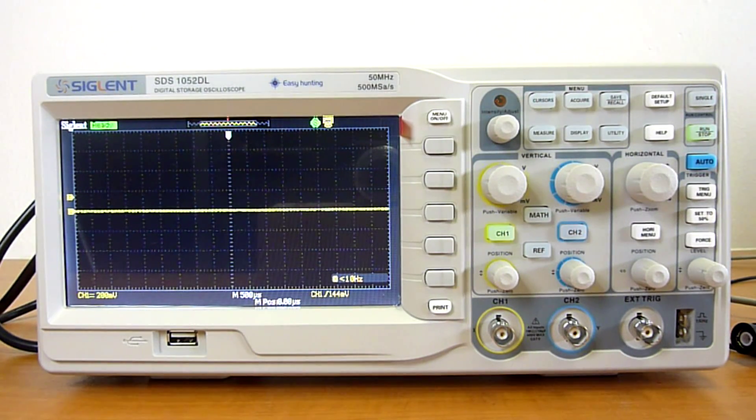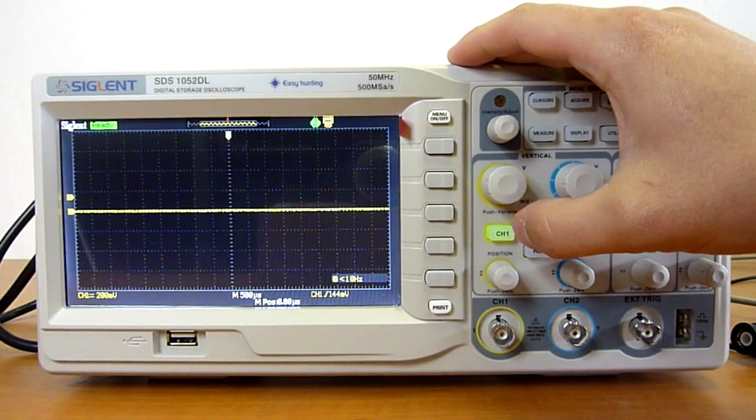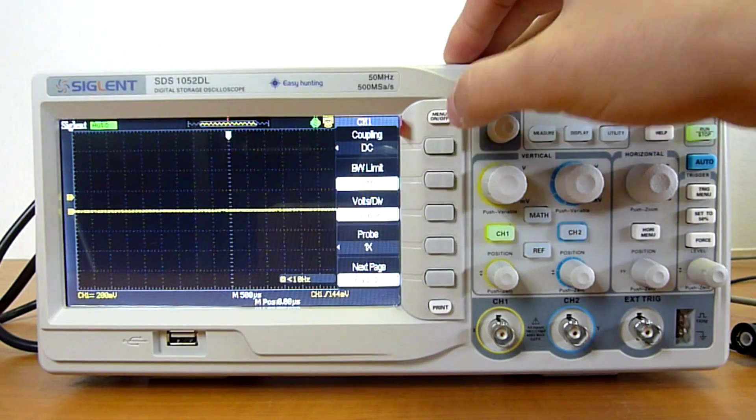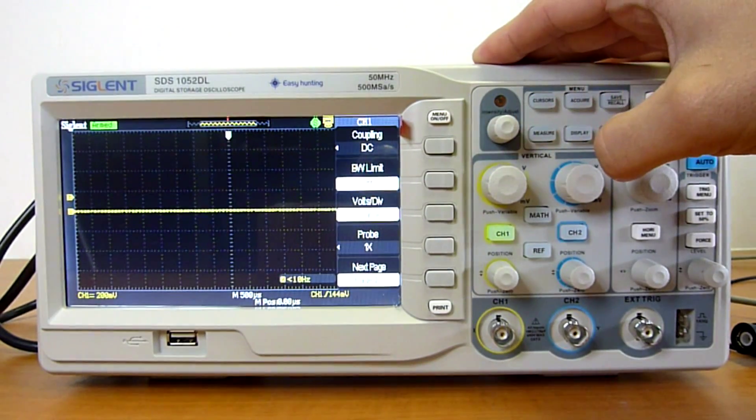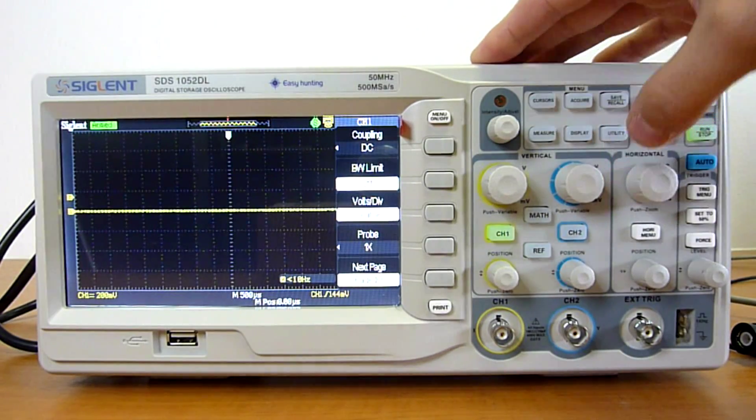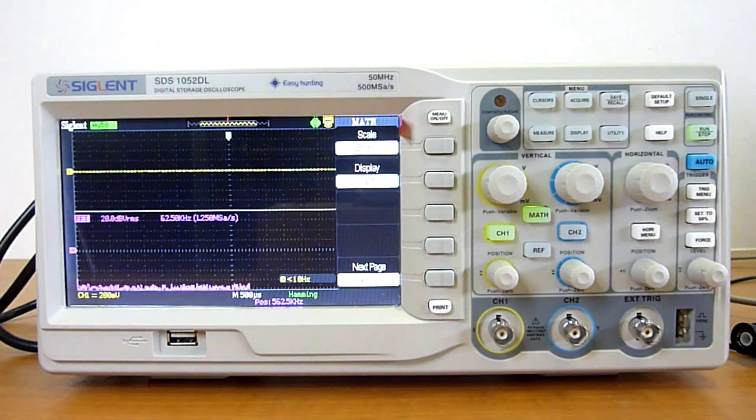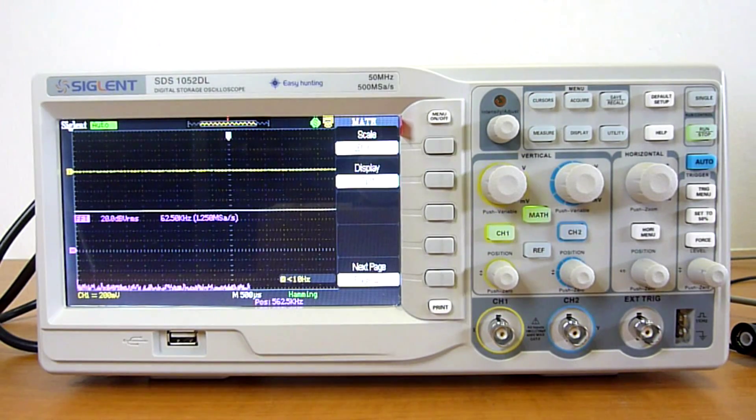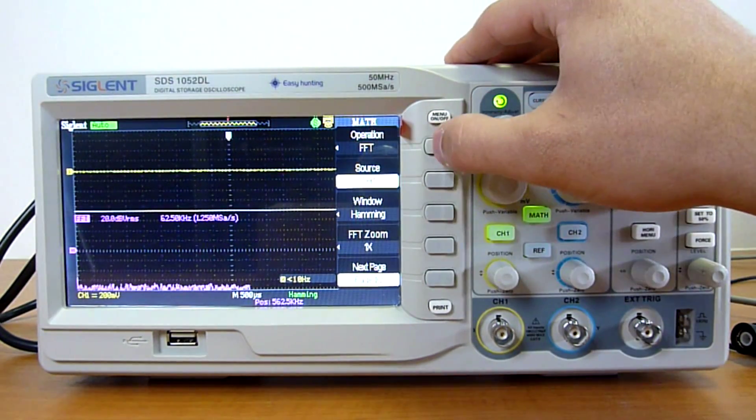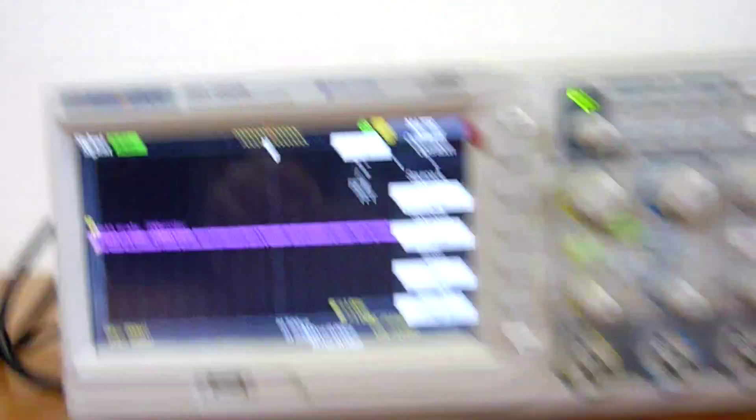Depth of memory is 32,000 points. And I really like the overall feeling of this product. And the menu is pretty intuitive. Let's look for example at the math menu. When you can perform several operations between the channels.